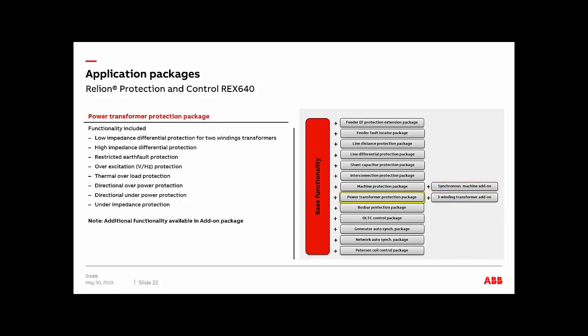Now moving on to a transformer. When it comes to the transformer, you're going to have low impedance differential protection as well, with 3 settable slopes and a high stage instantaneous differential trip. You're going to have restricted earth fault protection. You're going to have volts per hertz, protection number 24. Thermal overload protection is going to be available, directional overpower, underpower, and under impedance protection as well.